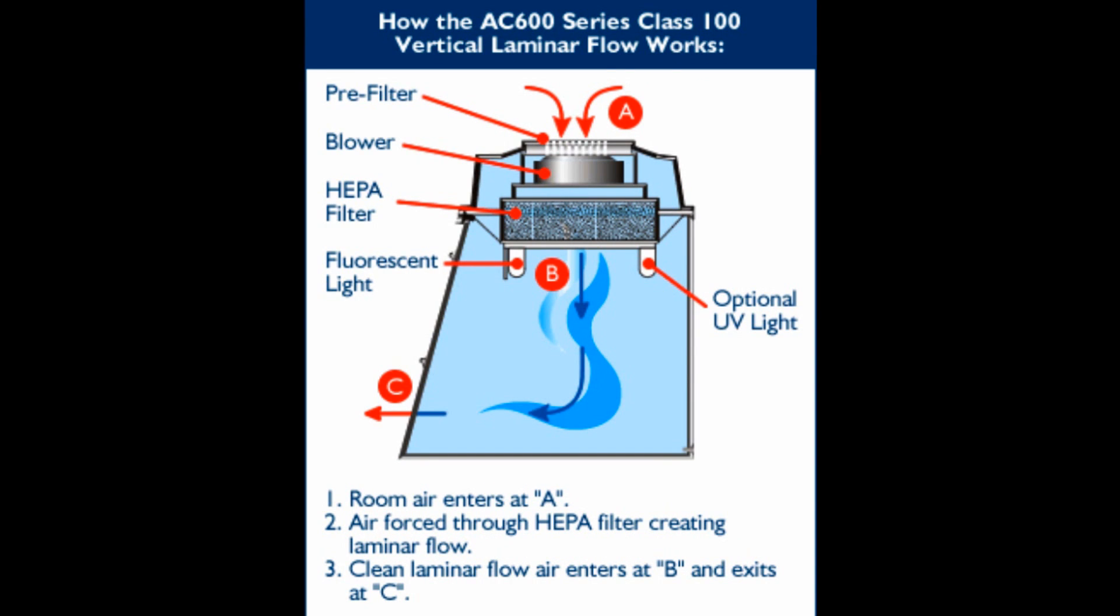How the vertical laminar flow works: Room air enters at pre-filter. Air is forced through HEPA filter creating laminar flow. Clean laminar flow air enters at B and exits at C.